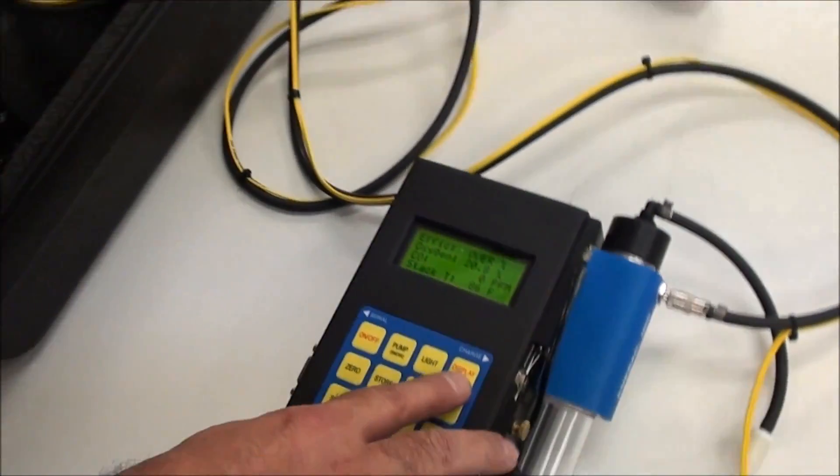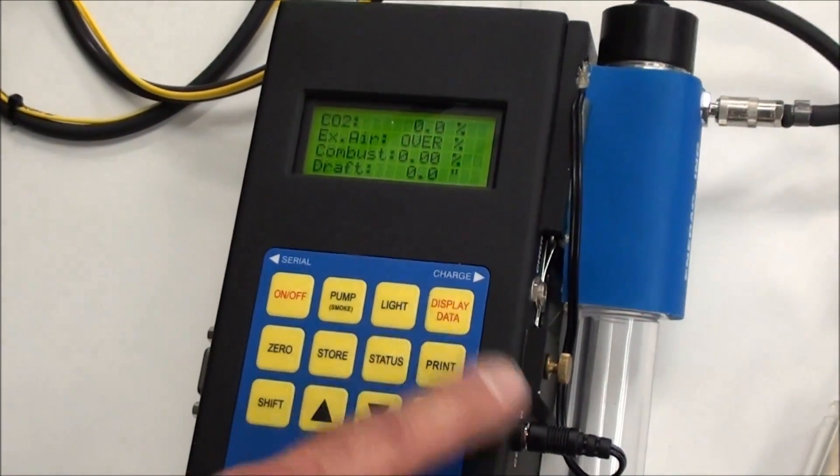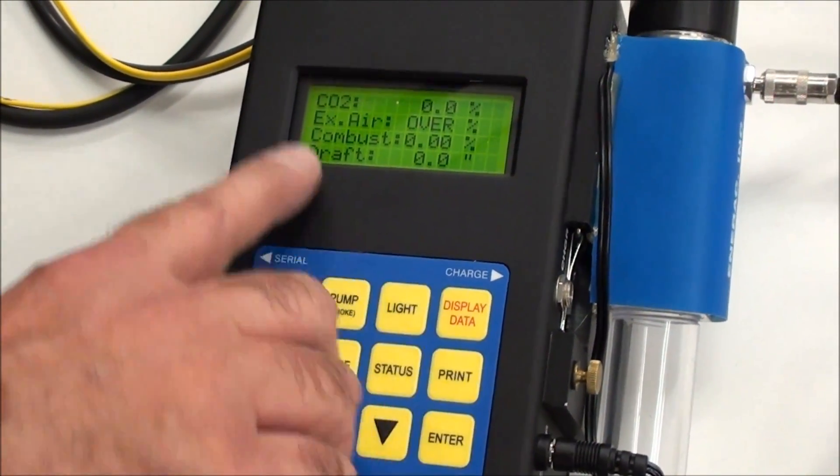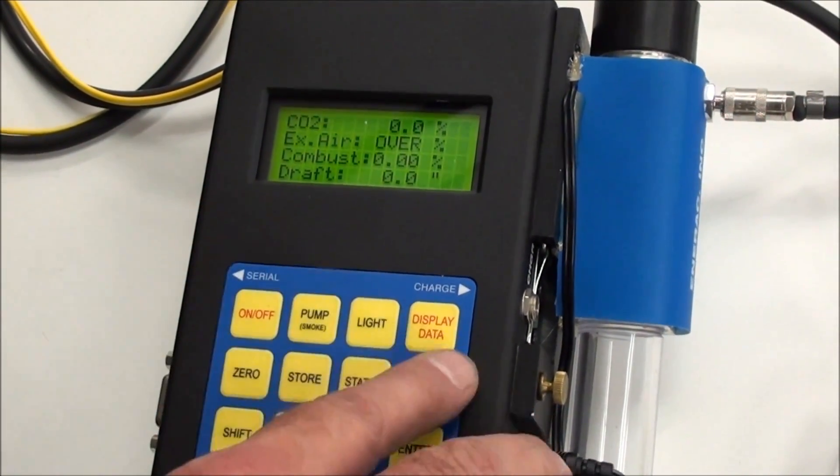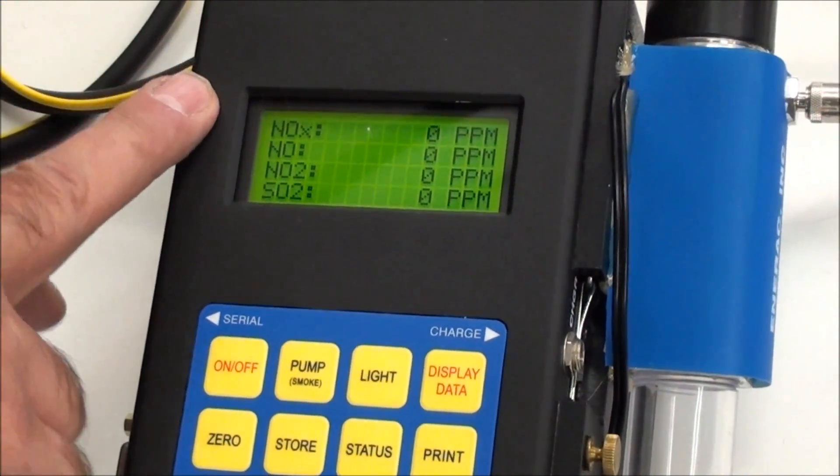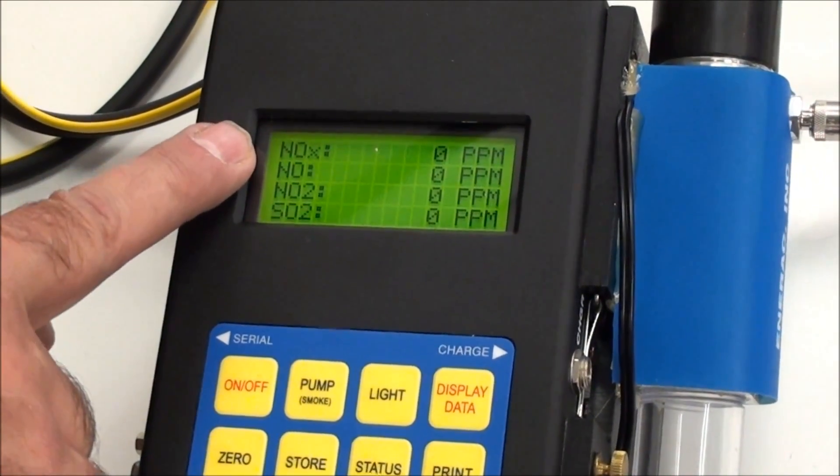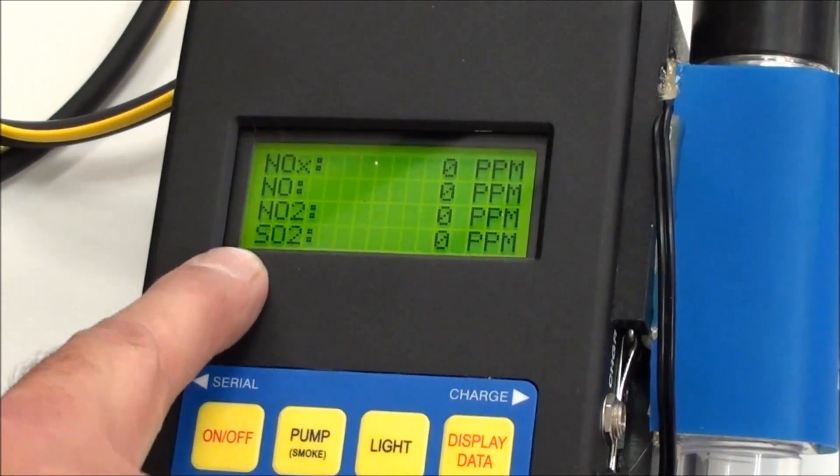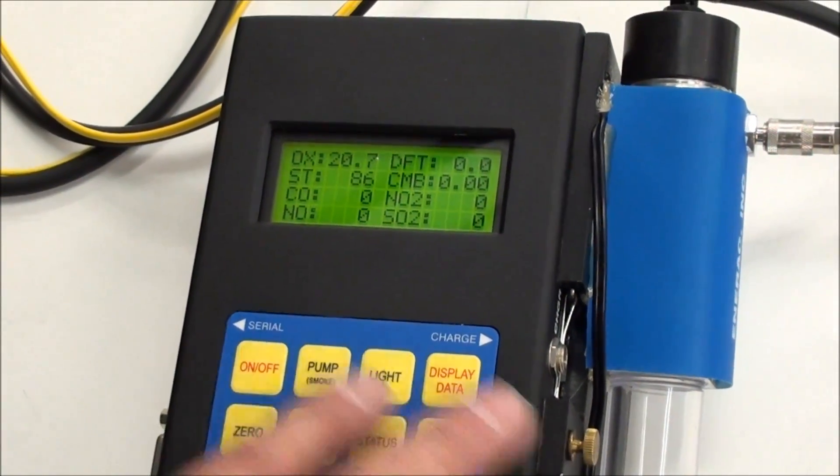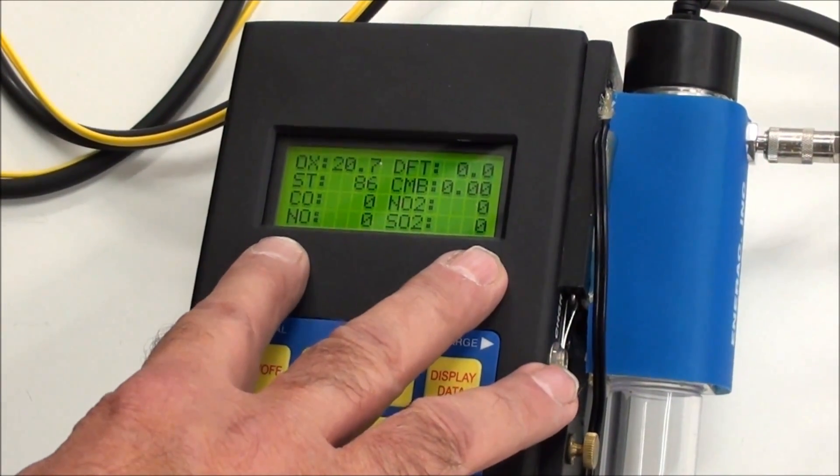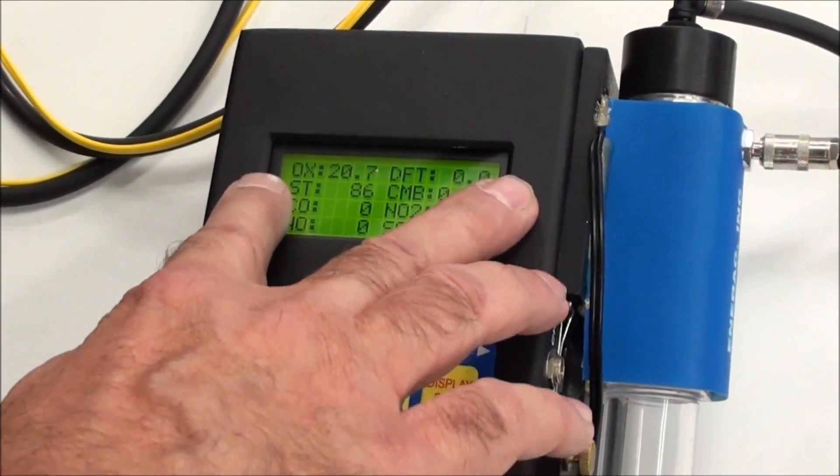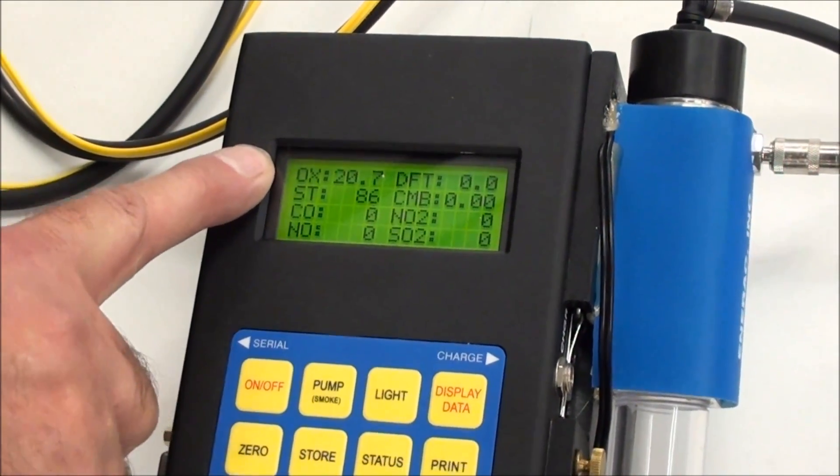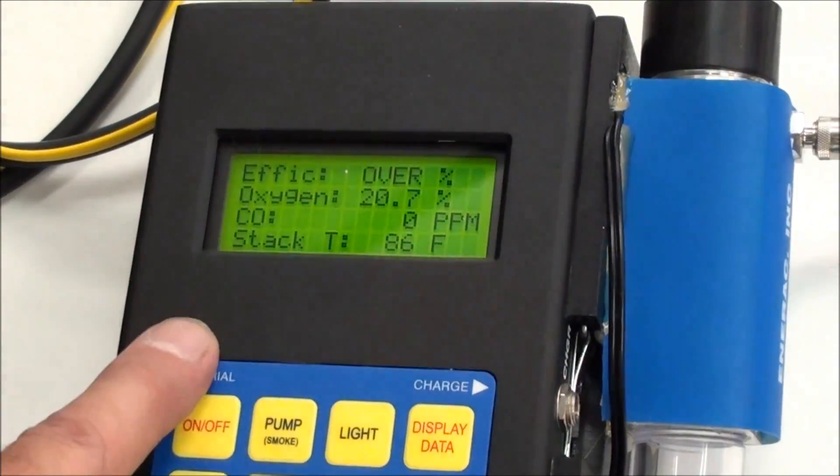Now what you'll do is you can check by simply hitting the display data button, and you toggle it through. You'll see on the second screen, you've got your CO2 excess air, combustibles, and draft. Next screen, these are your toxic sensors. The NOx is a total of the NO plus the NO2, and then you have the SO2. And the last screen is just a compilation. It gives you all the readings on one screen that you might be interested in. It shows you your toxics, your stack temp, your combustibles, your draft, and your oxygen reading. And then you hit it again. It goes back to the beginning.